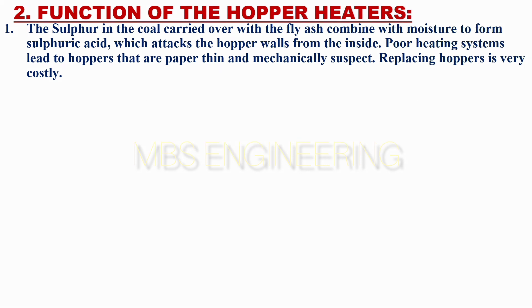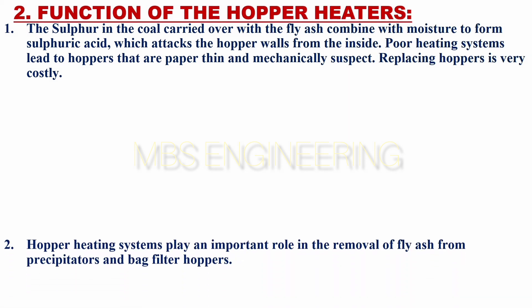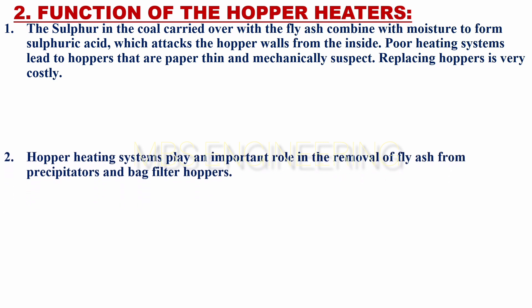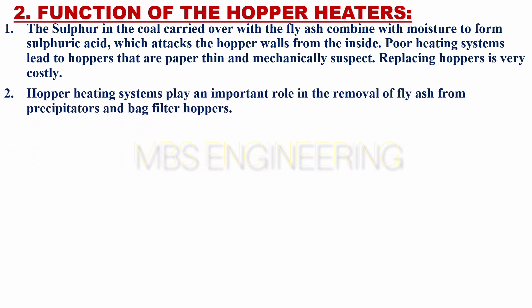The sulfur in the coal carried over with the fly ash combines with moisture to form sulfuric acid, which attacks the hopper walls from the inside. Poor heating systems lead to hoppers that are paper-thin and mechanically suspect. Replacing hoppers is very costly.